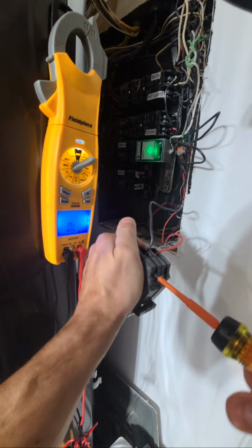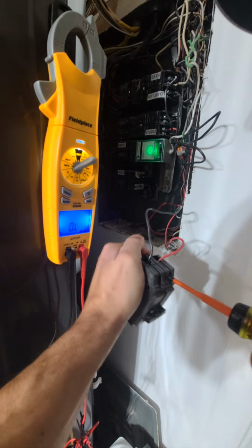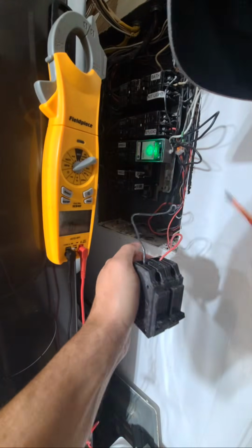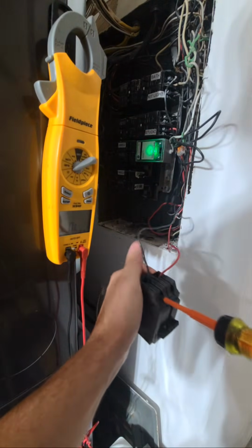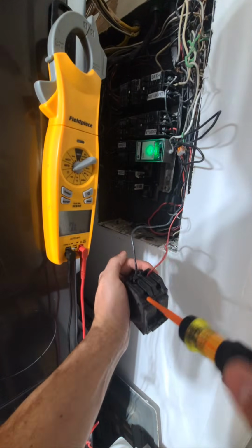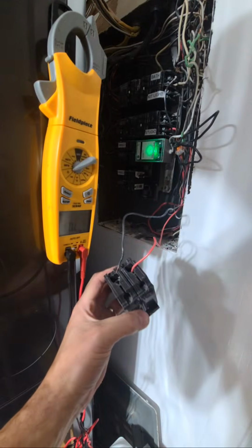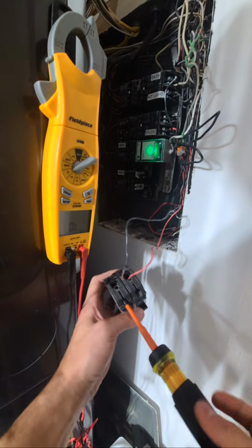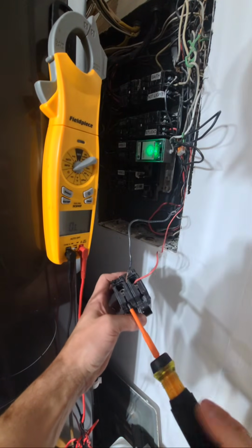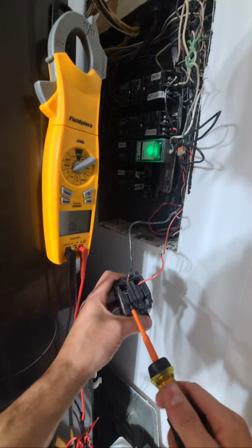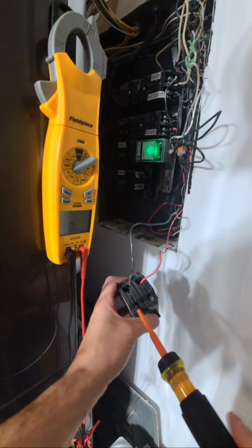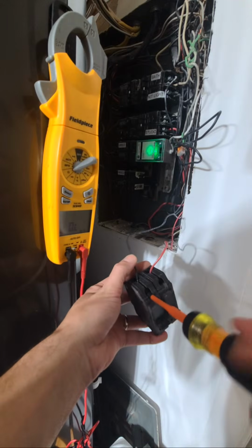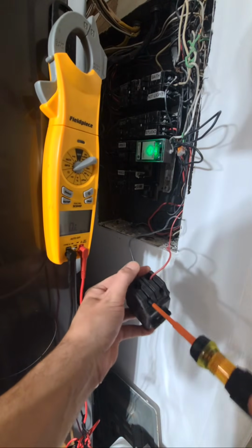I'm not happy with the way that it grabbed. We may have damaged this breaker the way that we were arcing inside of it, because it just does not want to grab like it ever did. Let's see here. Let's watch it close. Okay, I think it's good. Put it in there. It was just kind of off center. GE is not my favorite.